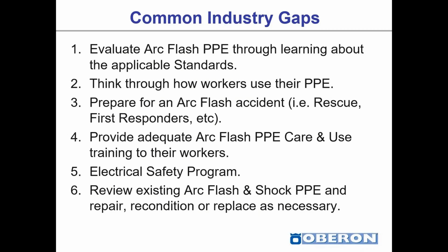Common industry gaps that we see out in the market: a gap would be to evaluate arc flash PPE through learning about applicable standards. I mentioned all those different standards previously. It is a lot like alphabet soup, so it's difficult, and hence it is an industry gap. We often see that employers aren't thinking through how workers use their PPE. They're not preparing for an arc flash accident, such as the rescue, first responders, providing adequate arc flash PPE care and use training to the workers, not having an electrical safety program, and not reviewing existing arc flash and shock PPE to identify what needs to be repaired, reconditioned, or replaced as necessary. So those are common gaps that we should be addressing.